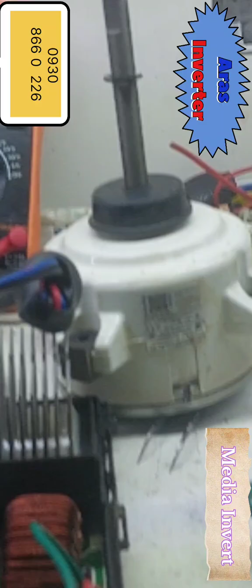The error indicates that the control board is sending a signal to start the outdoor fan motor, but is not receiving the expected feedback. This could be caused by a faulty outdoor fan motor itself, a damaged capacitor for the fan motor, or a break in the wiring between the PCB and the motor. Or the driver circuit on the main PCB that controls the fan motor has failed. This is a very strong possible analysis.